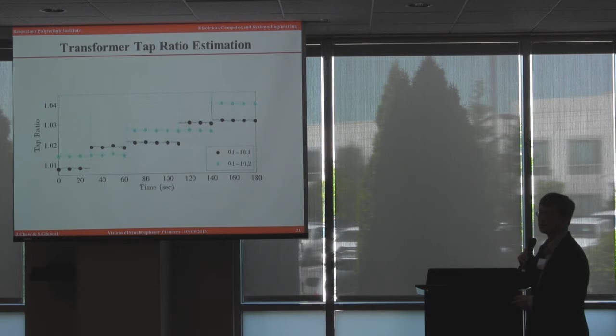One of the things that the synchrophasor standard looks at is accuracy. There is this thing called total vector error. For us, the question is how do we look at the accuracy of the PMU data over the network? There's no reference that we can use. So instead, we took the phasor state estimator solution and used it as the accurate reference value, and compared the measurements to it. Of course, we have to put the current scaling in this calculation, otherwise the number doesn't look very good. So we did put the current scaling in.